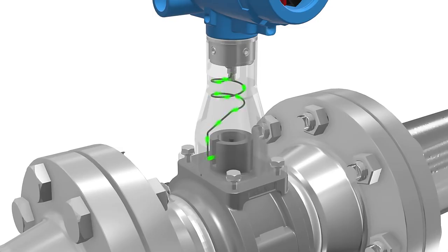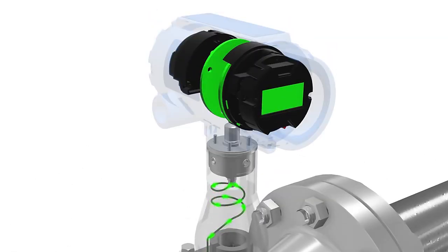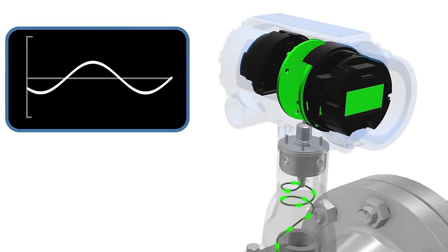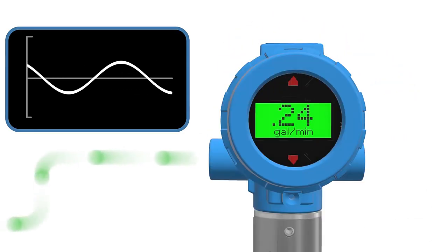Once a mechanical signal has been formed by the vortices passing by the shedder bar, a sensing element takes the mechanical motion generated by the flexure and converts it into an electrical signal. This electrical signal is then passed from the sensing element through a circuit up to the electronics board stack, where it is then processed and turned into a quantifiable velocity reading. This signal is then outputted to the vortex's local display and out to the control system.